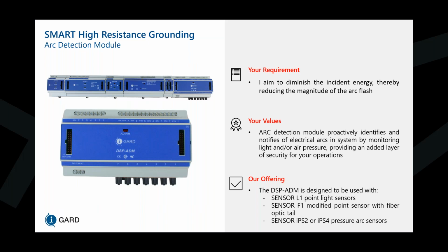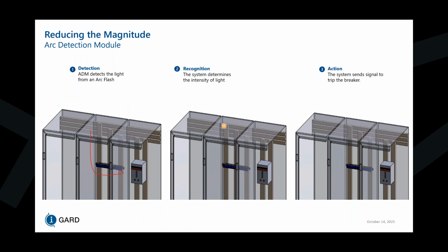Arc detection module proactively identifies and notifies of electrical arcs in the system by monitoring light and/or air pressure, providing an added layer of security for your operations. So our module is called the DSP ADM, and it can use point light sensors, modified point sensors with fiber optic tails, and IPS2 or IPS4 pressure arc sensors. The theory behind it is quite simple. The ADM detects the light or the pressure from an arc flash. The system determines the intensity of the light, and the system sends signal to trip the breaker if a certain threshold is exceeded.